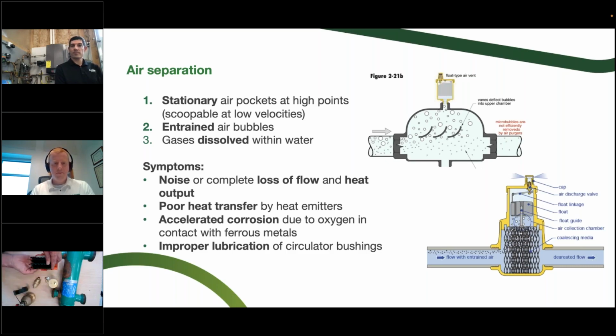If you would have built this with this inside there, you would have had a great air separator, because now you've got these little vanes that are catching the bubbles like we showed in the graphic on the slide there. But yeah, this is just intended to try and push the bubbles up where this can do its job to remove them. This one here has a port that maybe the expansion tank and the fill valve would hang on. So you've got your expansion tank and your air vent, but it's certainly not a high efficiency type of device. There's just nothing in there to get those entrained air and the micro bubbles out.